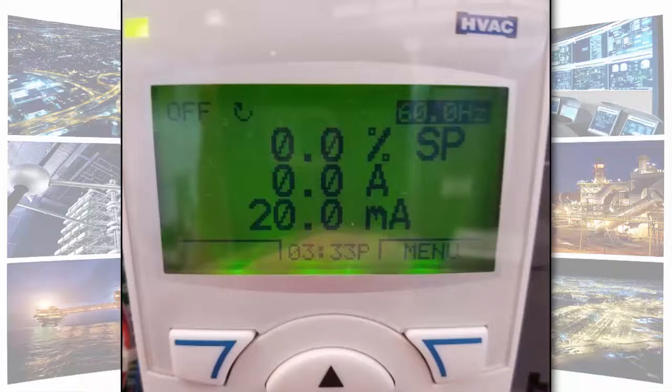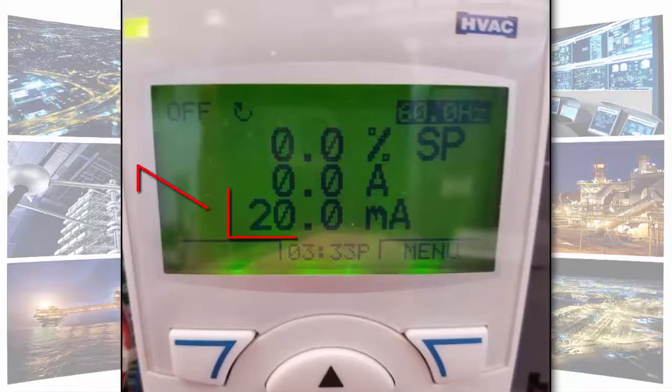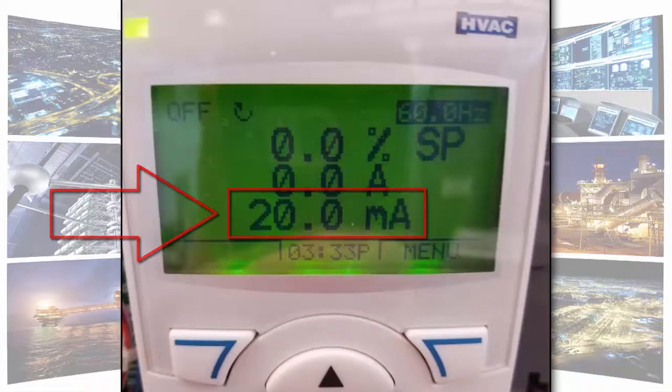This is a screenshot of the default home screen the way the drive would be received out of the box. You'll see the bottom line shows 20 milliamps. For this video we will modify the default bottom line of the display from 0 to 20 milliamps to 0 to 10 volts VDC.